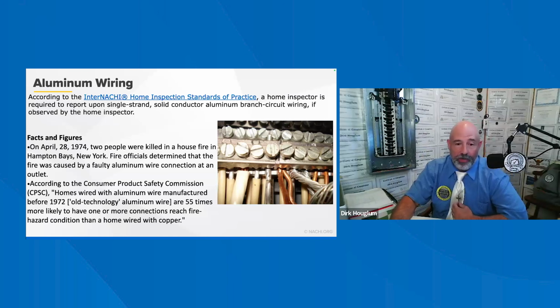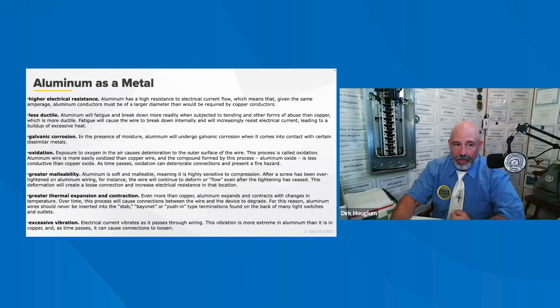Double tapping aluminum wiring and stuff, you don't want those tied together because it can cause a galvanic reaction, and you need a dielectric in between there. So you can't do that unless it's just short term termination points. So just FYI, aluminum as a metal. You can just screenshot this, make sure that you check out the galvanic corrosion. Aluminum is great, but it wasn't the greatest property to be using, and a lot of insurance companies really frown on that now.